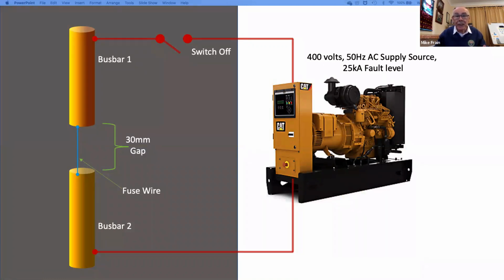Arc flash is usually caused by inadvertent contact between an energized conductor such as a bus bar or a cable with another conductor or earth. But simply, it's the insulation breakdown, and very often that insulation in question, in low voltage systems anyway, is simply air. Sadly, the cause of the insulation breakdown is very often human intervention. Some of the practical examples that I'll show you later exemplify that.